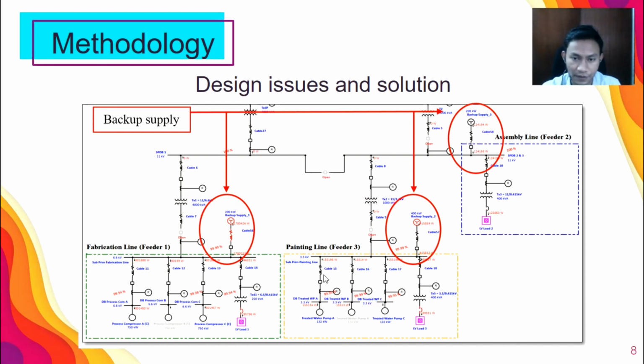so the load cannot continue with manufacturing their product. So the solution is to put a generator for each feeder, which is feeder 1, feeder 2 and feeder 3. Each feeder gets one generator only. For the specification, I will put the specification parameters in the full report.